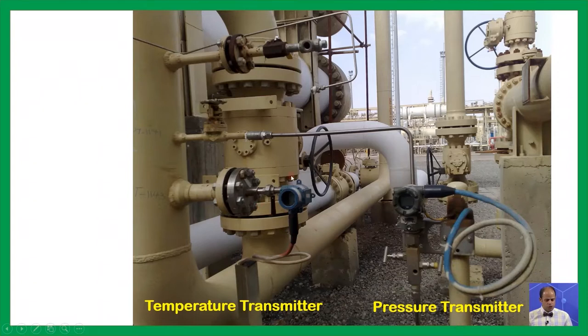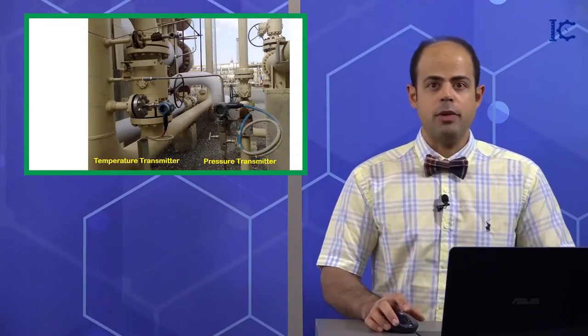So this temperature transmitter which was installed on the thermowell has the responsibility for measuring the temperature and finally send it to the control room via a signal 4 to 20 mA. Moreover, this pressure transmitter was installed on the manifold and actually was fastened with the help of a U-bolt and bracket on this unit. This one has the responsibility to measure the pressure and finally send it to the control room again via electrical signal, I mean 4 to 20 mA.